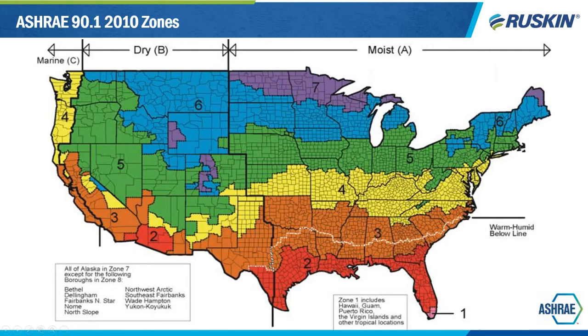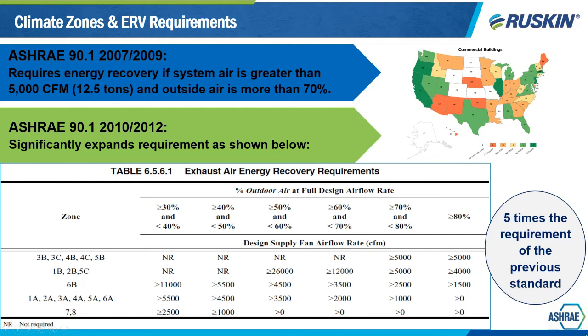Okay, so prior to ASHRAE 2007, there was no energy recovery code. Absolutely no code requiring energy recovery prior to 2007, okay? ASHRAE 2007 came out and stated that energy recovery is required if your system is greater than 5,000 CFM and if you are bringing in more than 70% outside air. Great steps in the right direction here. However, I don't know of too many systems where we're bringing in more than 70% of outside air. Definitely not our commercial buildings that we're designing here today. So while we got some energy recovery in the code, it did not really apply to our day-to-day activities.